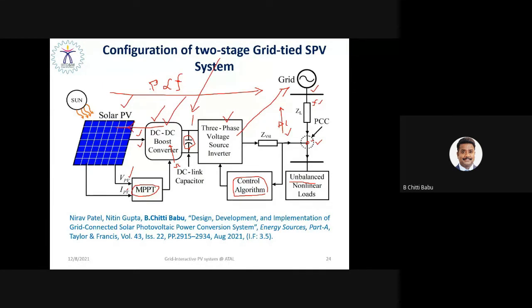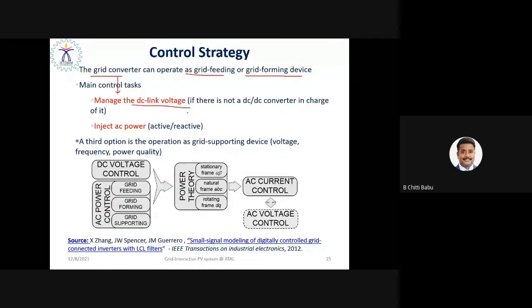So the active power must be regulated to maintain the frequency, meaning the power balance between the source and the load must be matched or balanced. If there is a balance between the source power and the load power, then the frequency remains constant. That active power balance is possible by maintaining the DC link voltage constant. So of course, the three-phase voltage source inverter with suitable control ensures constant DC link voltage control. So the main task is to maintain the DC link voltage constant in order to have a proper power flow between solar PV and the utility grid.